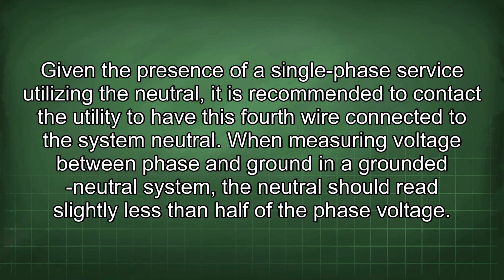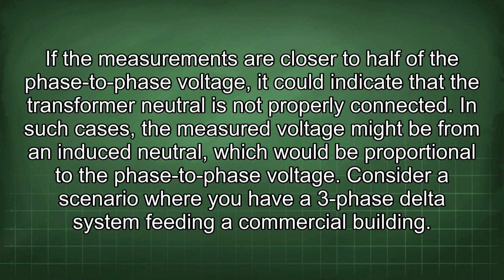When measuring voltage between phase and ground in a grounded neutral system, the neutral should read slightly less than half of the phase voltage. If the measurements are closer to half of the phase-to-phase voltage, it could indicate that the transformer neutral is not properly connected. In such cases, the measured voltage might be from an induced neutral, which would be proportional to the phase-to-phase voltage.